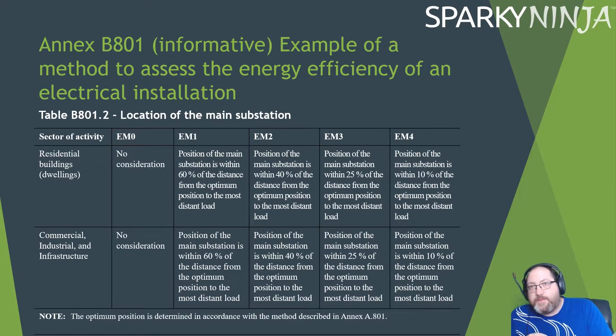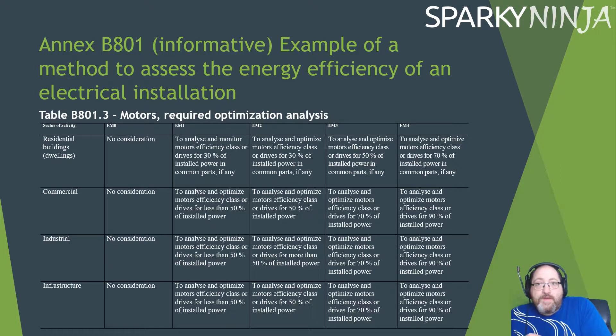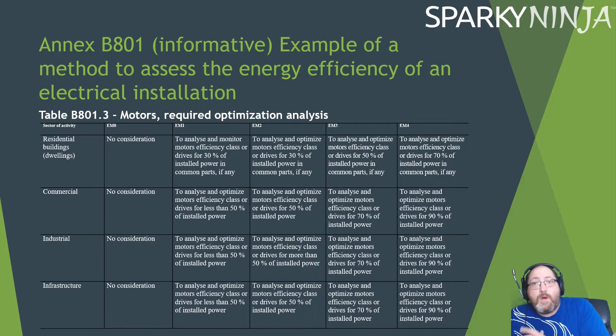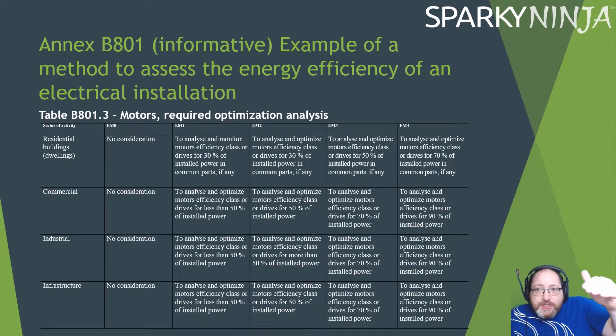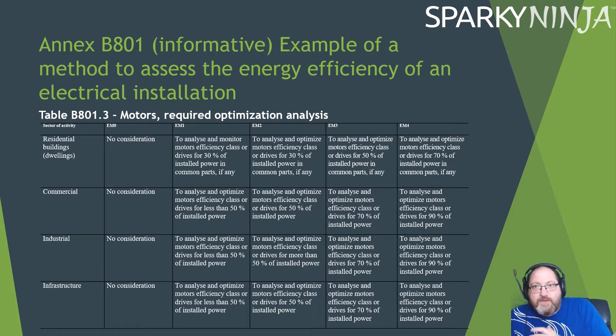For motors requiring optimization and analysis: no consideration gets zero. If you analyze and monitor motor efficiency class or drives for 30% of installed power, you get a one; to analyze and optimize gets a two. The threshold differs between residential and industrial — going from 70% to 90% — reflecting the difference between sectors. The work done to optimize motors is key here.